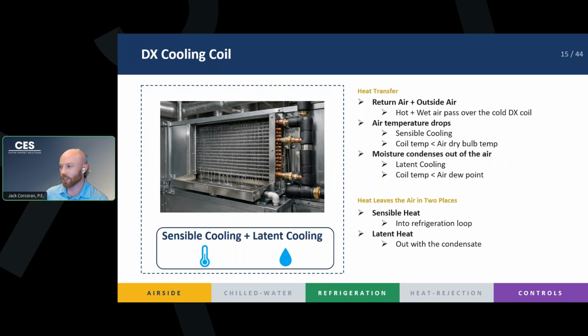So you can actually see at this coil, heat leaves the air in two places. As we said, it's sensible heat, right? Our air gets colder, right? So that heat from the air goes directly into the refrigerant. The refrigerant changes phases, as we talked about last week. The refrigerant changes from liquid into vapor, and so that goes out and rejects to the atmosphere. However, we're also going to get rid of heat in our condensate, right? So all the sensible heat goes into the refrigerant, but just because we're colder than the dew point of the air, we're going to actually condense the heat and the moisture out of the air as condensate, and that has to drain out of the unit to a floor sink or to a sink or a floor drain.